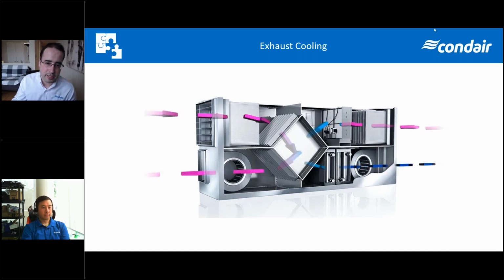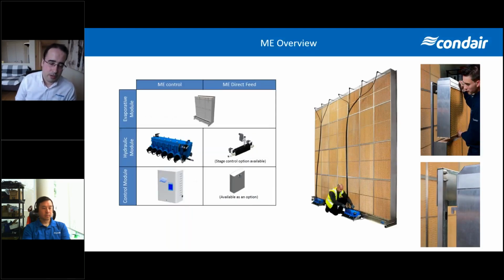Another application you can see here is if you put your evap system in your return, you can also cool as much as you can because you're exhausting that air, so you don't really care. You can go up to 95, 96%, and then use heat recovery for sensible heat recovery to cool down the incoming air that you supply to your data center in this case. So like you can see, there are different types of application you can use. Depends also if you want sensible and latent or only sensible cooling. So like I said, we have our ME system. It's a system that uses glass fiber.